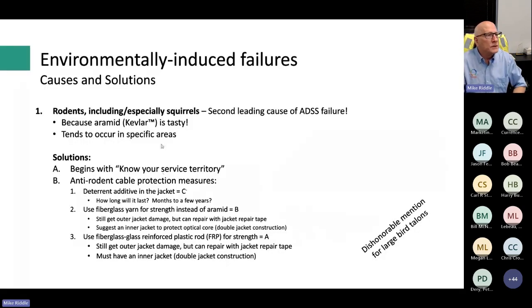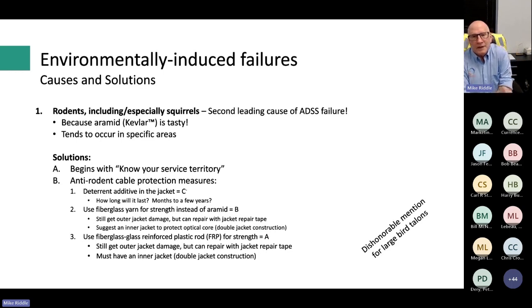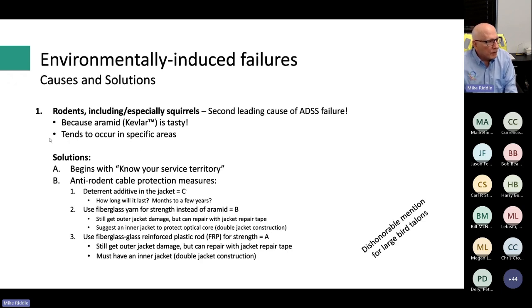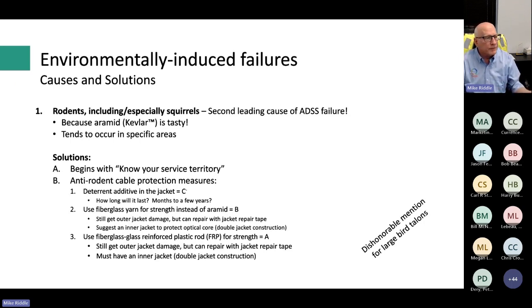Rodents — especially squirrels — are the second leading cause of ADSS failure, a close number two to gunshot damage. Squirrels and rodents are simply not deterred by aramid, more commonly known as Kevlar. This tends to be a problem in specific areas. As far as solutions, know your service territory and plan accordingly, but here I can offer some potential technical solutions.